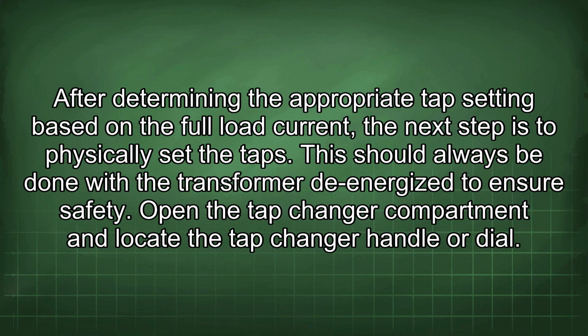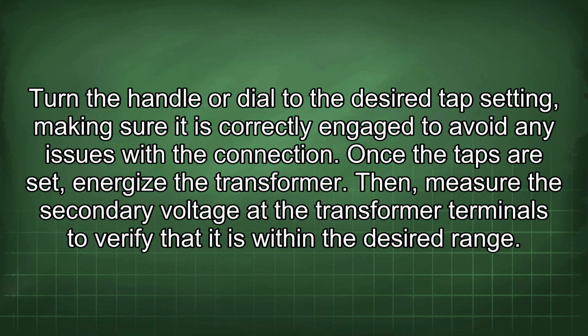After determining the appropriate tap setting based on the full load current, the next step is to physically set the taps. This should always be done with the transformer de-energized to ensure safety. Open the tap changer compartment and locate the tap changer handle or dial. Turn the handle or dial to the desired tap setting, making sure it is correctly engaged to avoid any issues with the connection. Once the taps are set, energize the transformer.